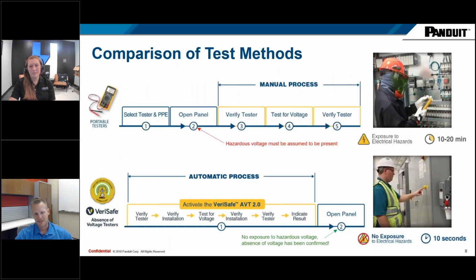Comparing the two methods side by side, in a very dumbed down, very simplified version, right? Compare the two tests. You've got your tester and putting on your PPE. You're opening your panel, and at that point, because you're opening the panel and you haven't confirmed absence of voltage, you have to assume that hazardous voltage is still present, right? And then you go through and you test your tester, test the voltage, test your tester, do that live test, and you are exposed to electrical hazards. Caitlyn's example before was kind of a scary example, right? You've got that panel door open and he was exposed to hazards. Thank goodness nothing happened. That typically takes 10-20 minutes, could be longer, could be shorter, right? All depends on the facility and a lot of other factors there.